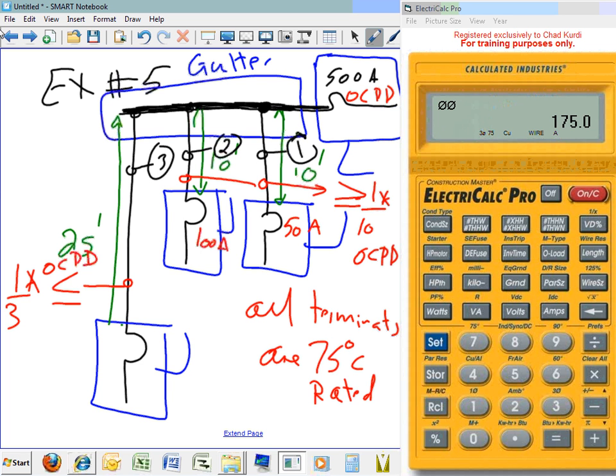So you go to the table under 75. If you know the terminals are 75, size a conductor. If you don't know the terminals are 75, 100 or less, you go to where? 60. Now you go to this. If it's 1,000, you multiply this by a third. The third of 1,000 is 333.3, right? 333 amps. A third, if you want to tap 25 feet.